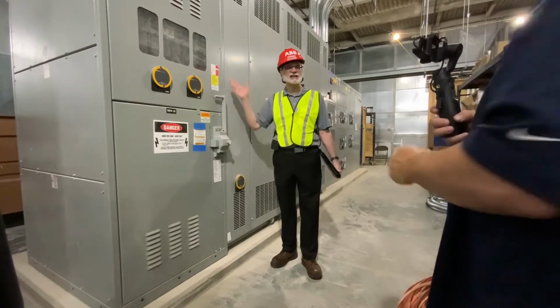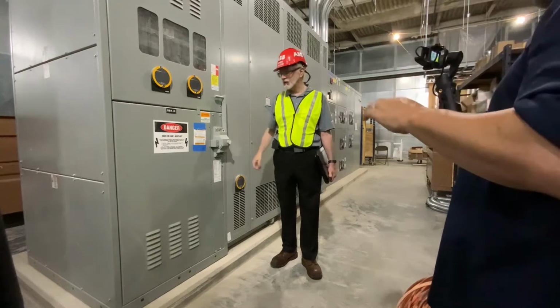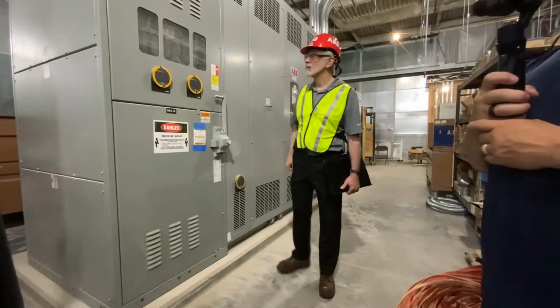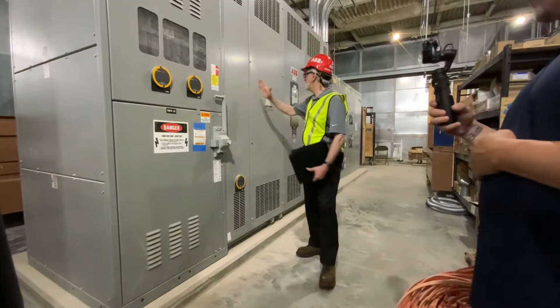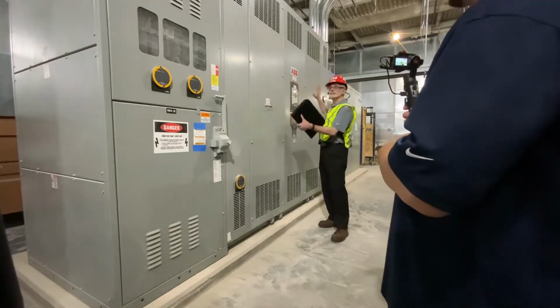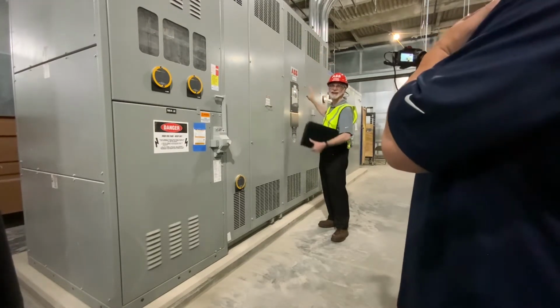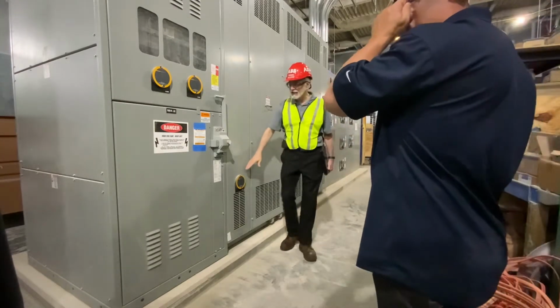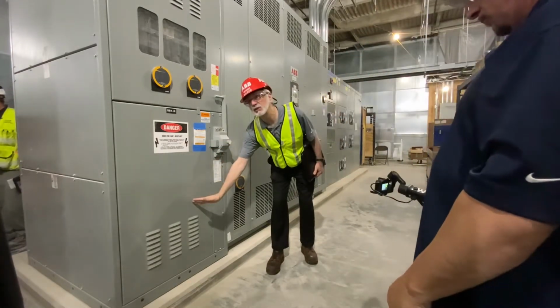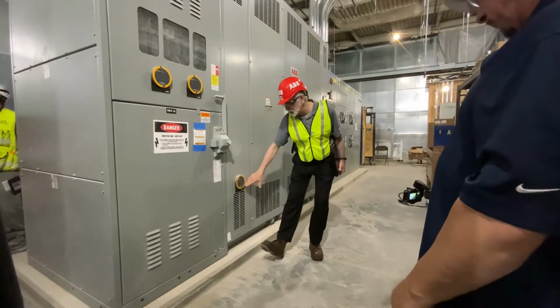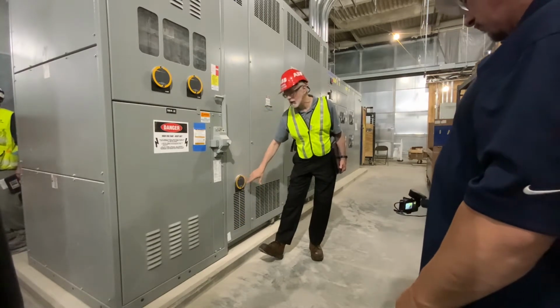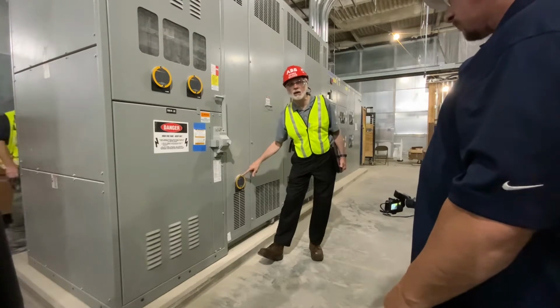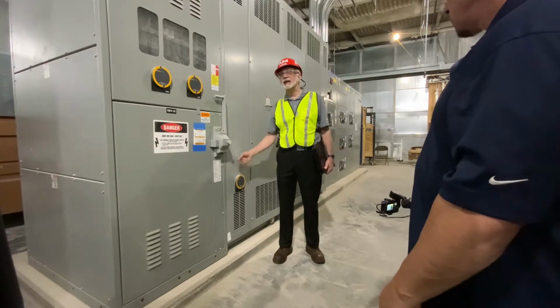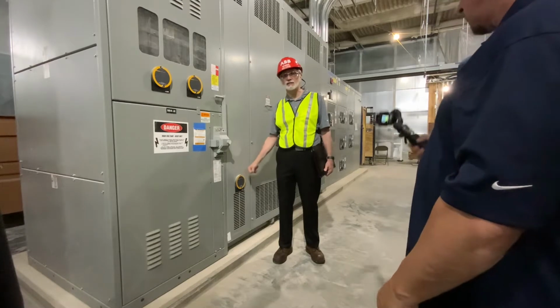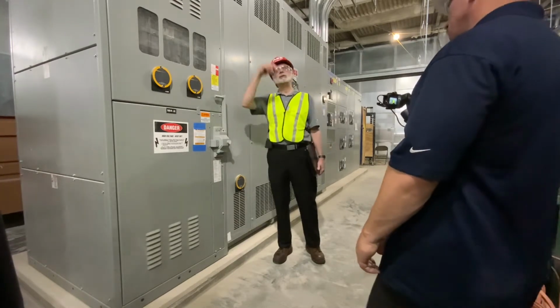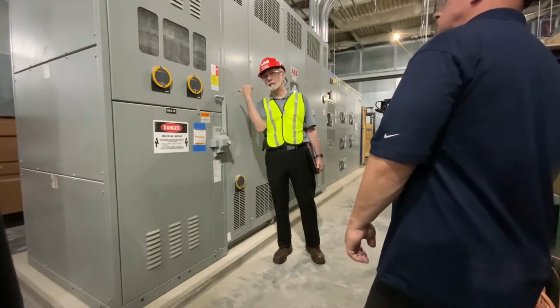This is pretty basic. Come in the back, goes over to the front. It is a cable connection. 13.2 here? It is 13.2 to here, and it is 13.2, sort of in the middle here. Okay, so what we have is a cable connection here from the bottom of the fuses all the way over to the connection to the transformer. And that's what this IR port is here, so that I can check to see if that cable connection to the transformer is also a good connection, just like the cable connection in the back of the equipment.